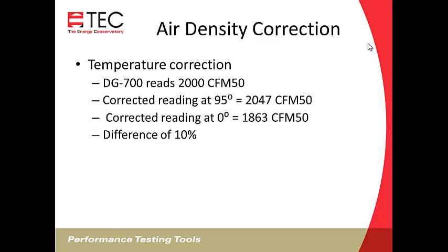So that can be significant. Or if you're doing a code compliance test, and you're close to that 3 air changes per hour, not making that temperature correction can make the difference between a pass and a fail, depending on what temperature it is.